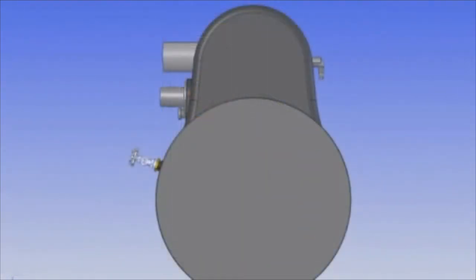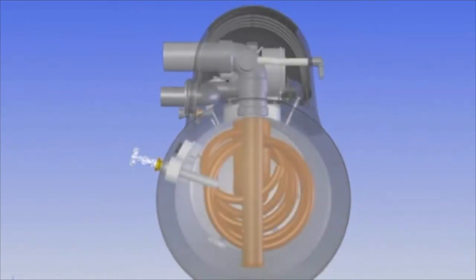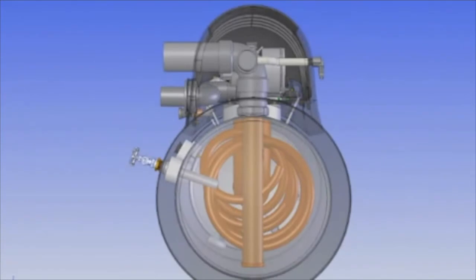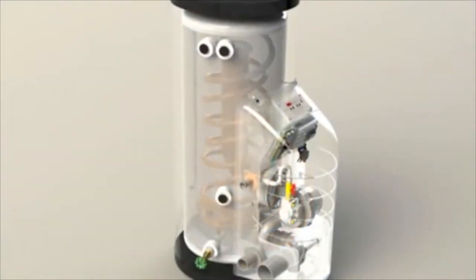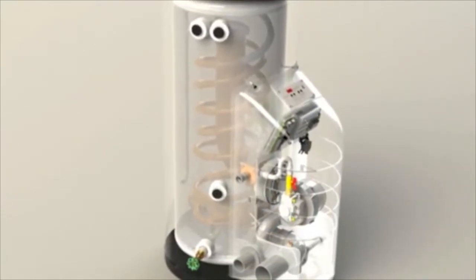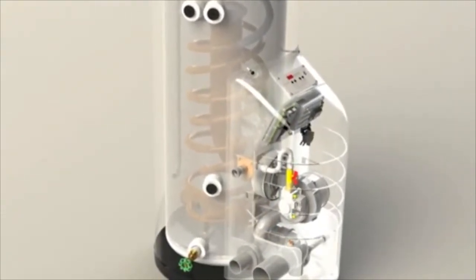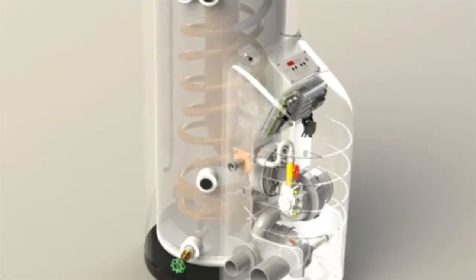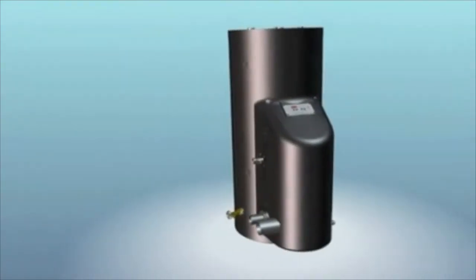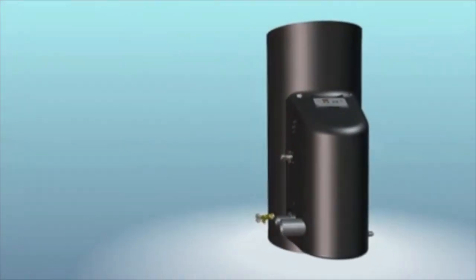Installed in a 55-gallon stainless steel tank, the heat exchanger is constantly surrounded by enough water to avoid flashing, which is a common concern in low-mass technology. Exchanging sensible heat at the top of the heat exchanger with the hotter water in the upper half of the tank, the flue gas, decreasing in temperature, flows back down through the low-temperature inlet water, cooling below its dew point, taking advantage of latent heat.